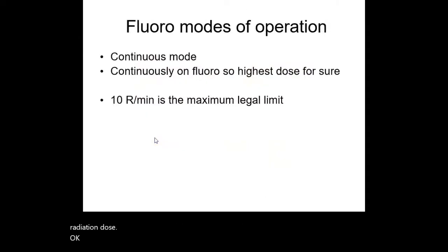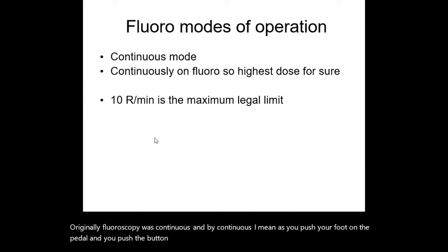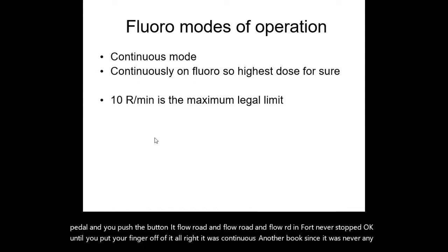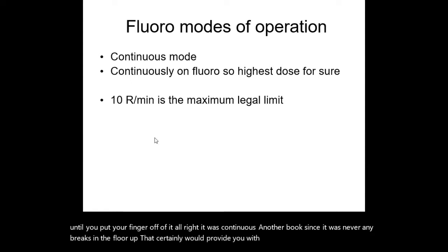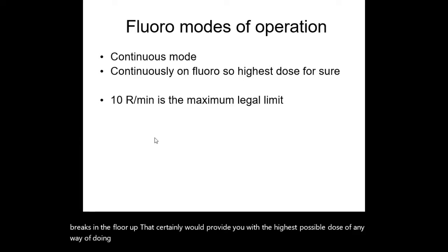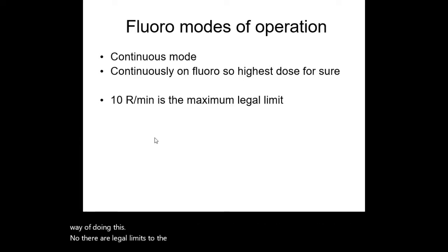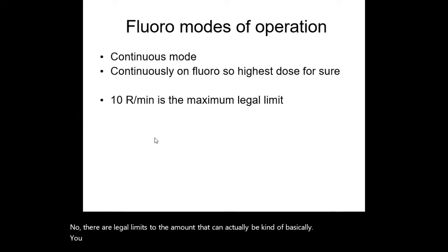Okay, now there are other ways of looking at this, one of which is how we actually operate these things. Originally, fluoroscopy was continuous. And by continuous, I mean you push your foot on the pedal, or you push the button, and it fluoroed and fluoroed and fluoroed, it never stopped until you took your finger off of it. Since there were never any breaks in the fluoro, that certainly would provide you with the highest possible dose of any way of doing this. Now, there are legal limits to the amount that can actually be exposed. You notice it says 10 roentgens per minute. And boy, it's a fair bit. This is one of the reasons why people go fluoro for hours on end.